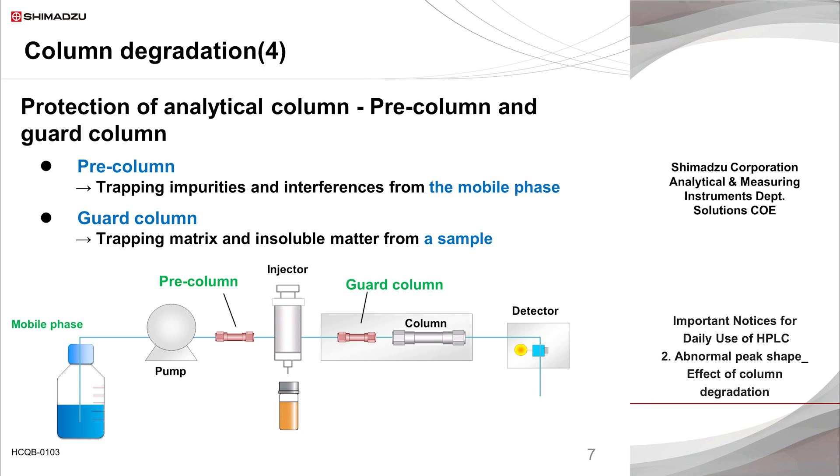In contrast, a guard column is installed between the sample injector and the analytical column. It is generally placed inside the column oven. Of course, the sample passes through the guard column and interacts with its packing material before being introduced into the analytical column. It is easier to understand the function of a guard column if it is considered as a detachable part of an analytical column, fixed at the column inlet where the packing material tends to deteriorate. Therefore, the guard column generally contains the same type of packing material as the analytical column of the same or smaller inner diameter and is shorter in length than the analytical column.